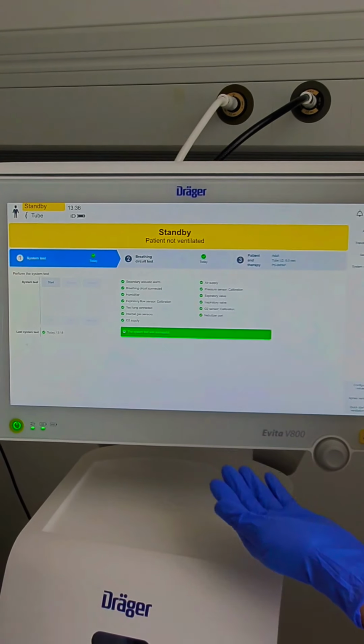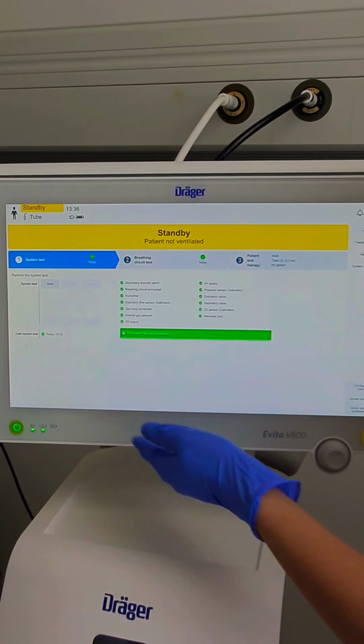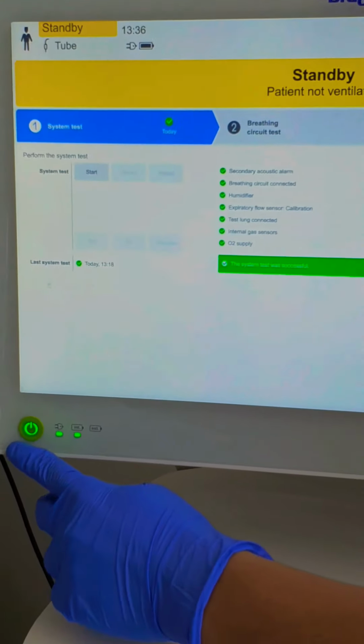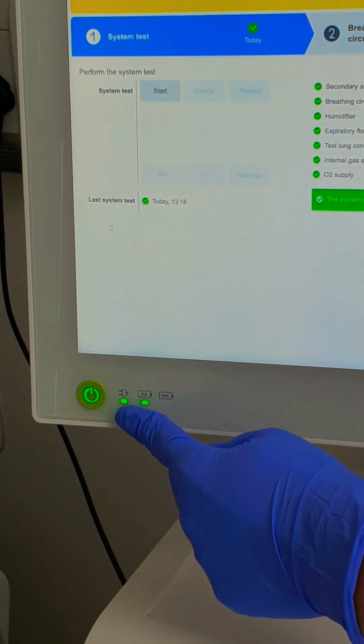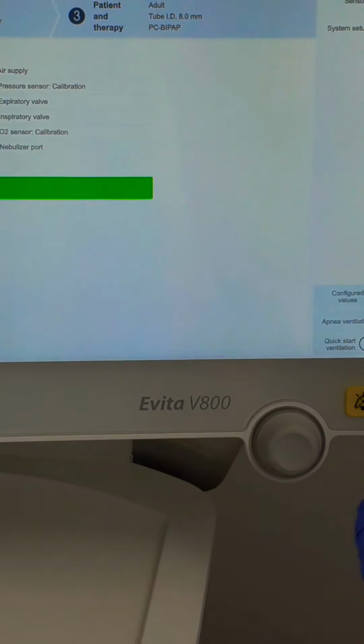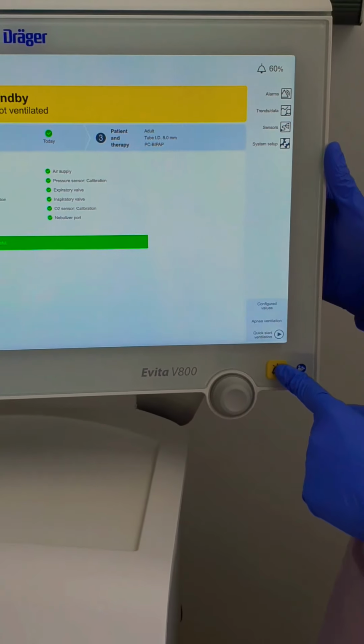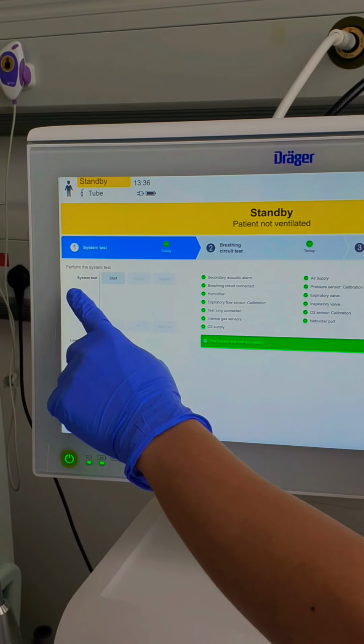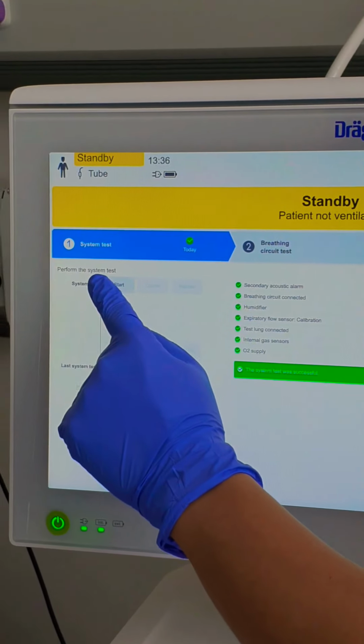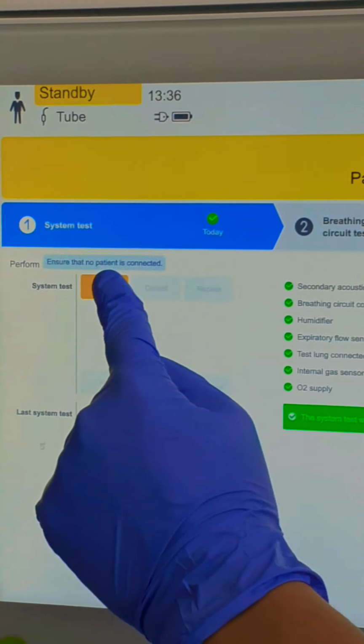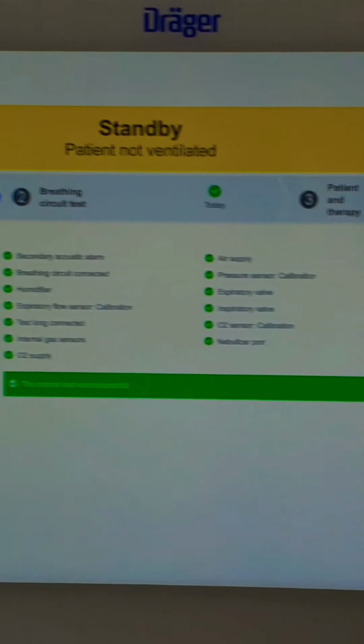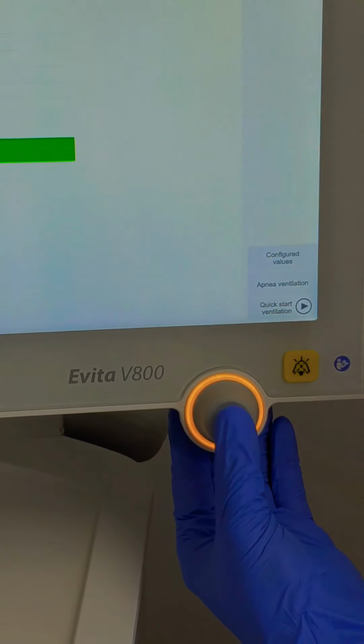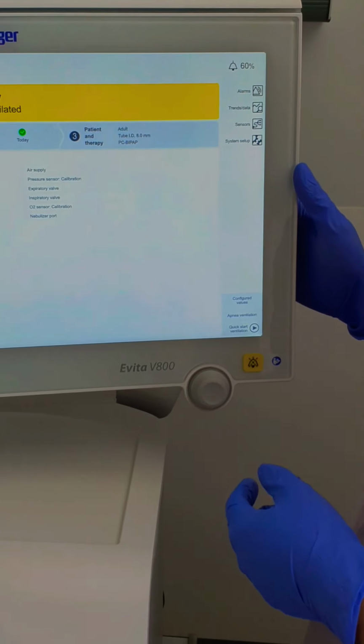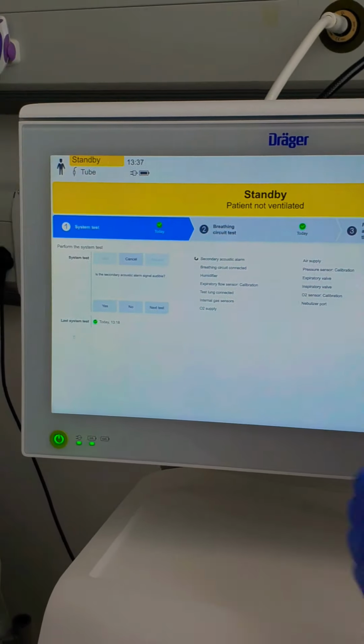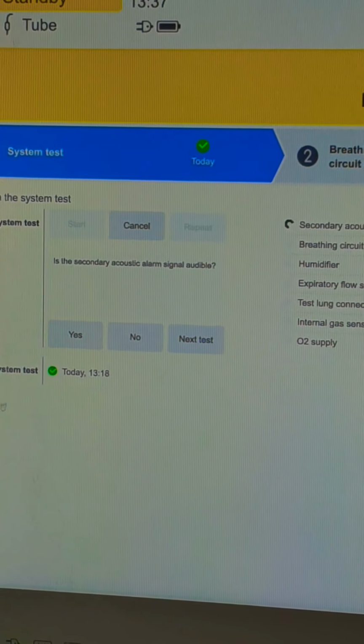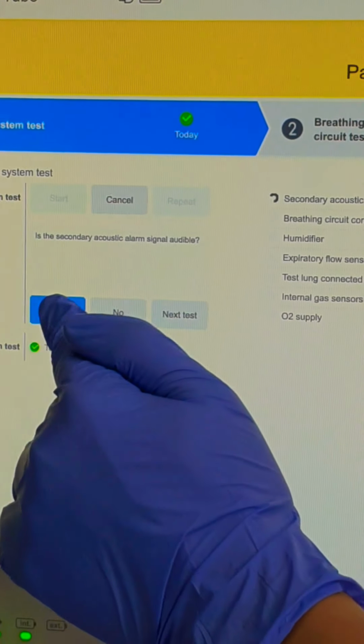Again, this is the Dräger Evita V800 ventilator. On the screen, there is a power button right in the left corner of the machine, and there is a battery indicator. Over here is your rotary knob and your silence alarm button. We're going to start the SST by pressing the start button right under the system test. If you press on that, it will turn amber, and the rotary knob also lights up amber. You just need to confirm it by pushing on the rotary knob. It asks, is there a secondary acoustical alarm signal audible, so you can hear it? Then you press yes.